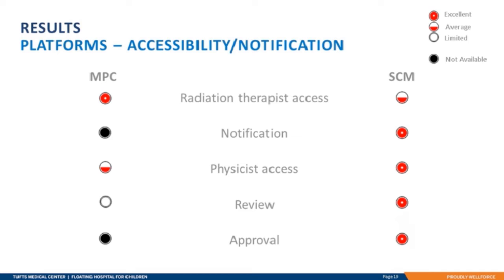Another area that we found SunCHECK Machine to stand apart in is the accessibility realm. Machine Performance Check is easy for the radiation therapists to access since they are already on the Linac console. But there are no notifications of failed tests. While nice to have, the offline mode of Machine Performance Check is more difficult to access for physicists, and reviewing the individual test group results requires a lot of clicks. Also, there is no approval option to mark tests reviewed.